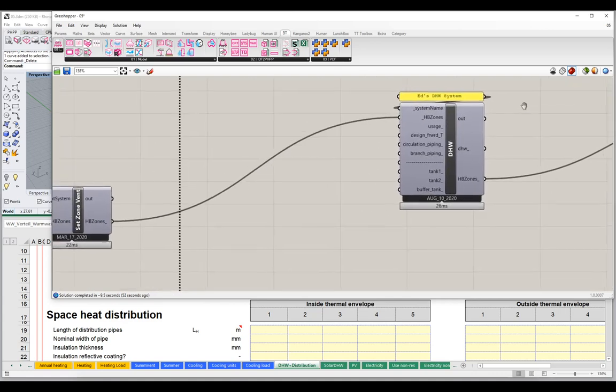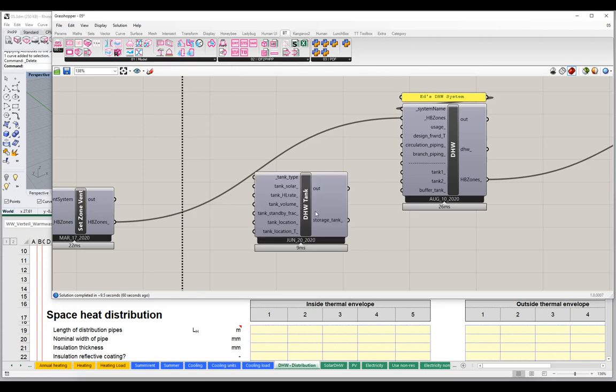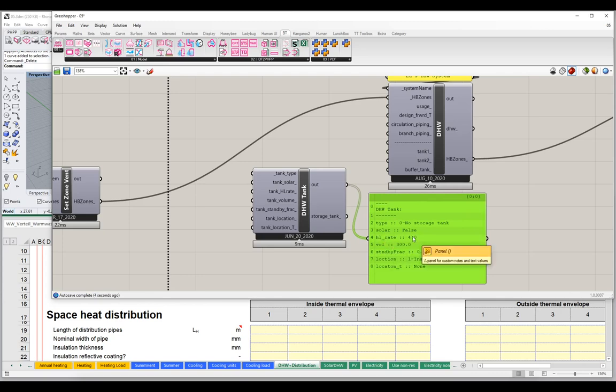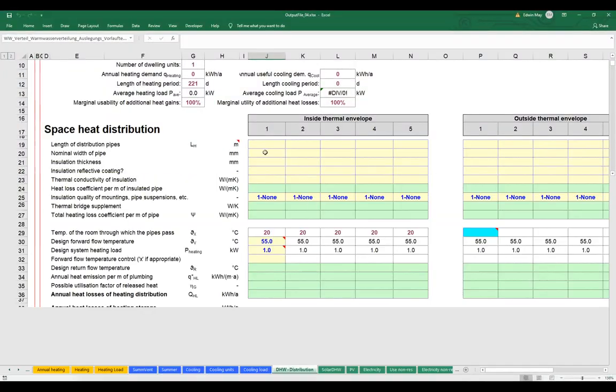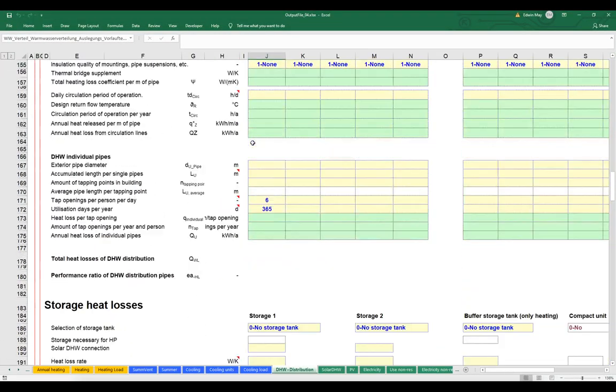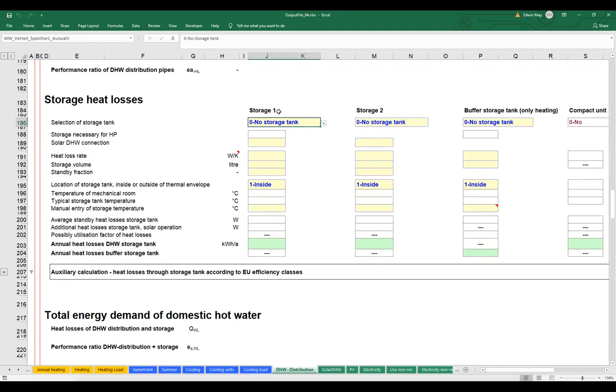Now I have a domestic hot water tank. What are we getting by default? We're getting a tank that has a heat loss rate, a volume, a standby fraction, and a location — it knows it's inside. But it is set to type zero, which is a 'no storage tank.' The PHPP options for tank type are: zero for no storage tank, one for a domestic hot water and heating tank — so if you have a hydronic system with a tank supplying radiators — and two for a dedicated domestic hot water tank not coupled to the heating system.